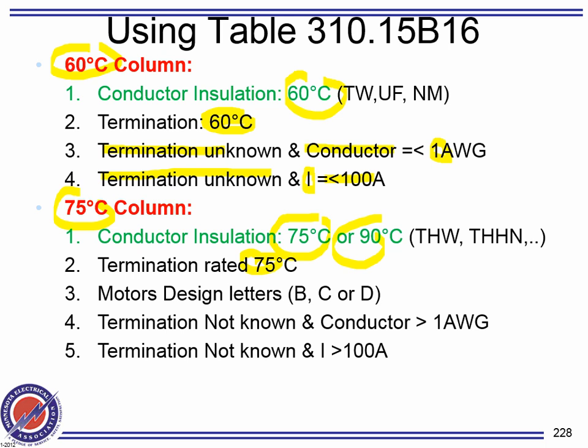Or if it's a motor, if you're designing a motor and it's designed B, C, or D, B, C, D motors are by code, 110.14 tells you these guys are UL listed with the lugs on them for 75, so don't worry about it. Or if the terminations, you have no idea what the lugs are rated for, but the conductors coming out of the machine are more than 1. There will be 1 aught, 2 aught, 3 aught, 4 aught. Once you see anything in the aughts and higher, and the installation is 75 or higher, where do you go? You're going to go directly into the 75.